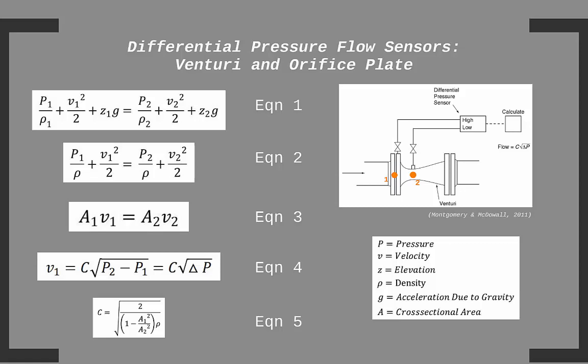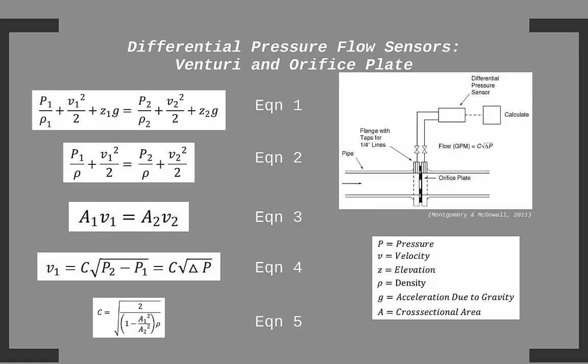Since equation 4 is the basic working principle for several of the sensors in this category of differential pressure flow sensors, we need to provide a better explanation than what the Montgomery and McDowall text provides. So in essence, we are just measuring the differential pressure between the two locations and solving for the upstream velocity. If it is the volumetric flow rate we are wanting to measure, for example CFM of air or GPM of water, we would just multiply this velocity by the cross-sectional area of the upstream pipe or duct. Orifice plate flow sensors and Venturi flow sensors can be used to measure liquid flow rates, and both work the same way. The difference is just that an orifice plate has an excessive pressure drop for not that much additional accuracy. Thus, it is not often used in HVAC applications.